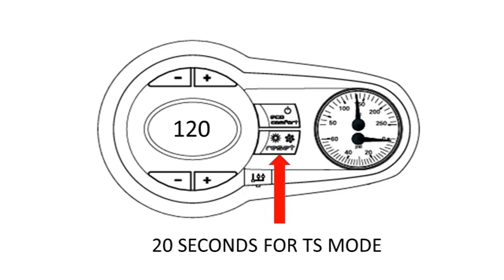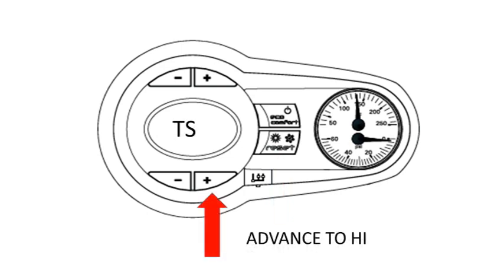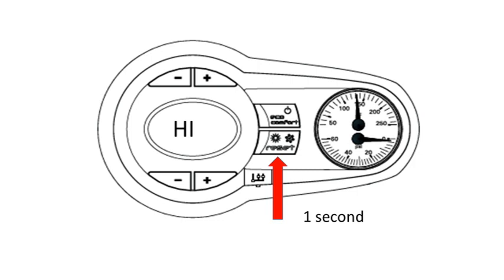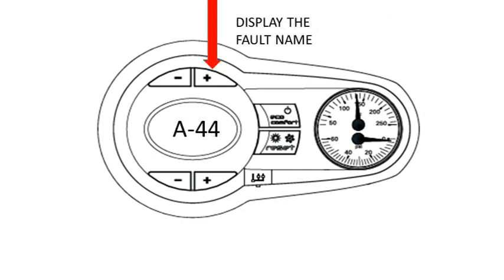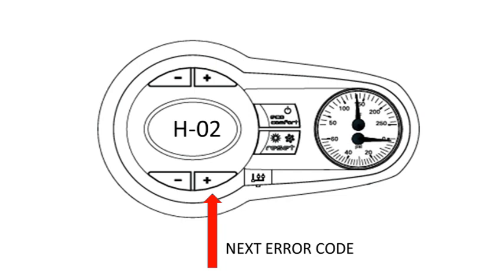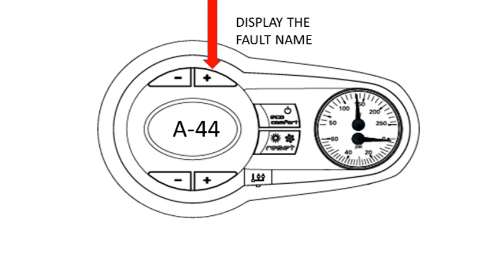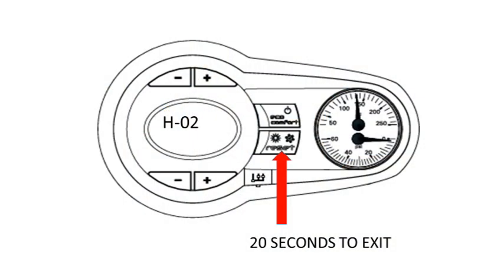If you need to look at the history of the error codes, press the reset button for 20 seconds. TS will be displayed. Press the bottom plus button until HI is displayed, then press reset for one second to enter the history mode. H01 will be displayed. Press the top plus or minus button to display the fault code. To exit this mode, hold the reset button for 20 seconds to return to the home screen.